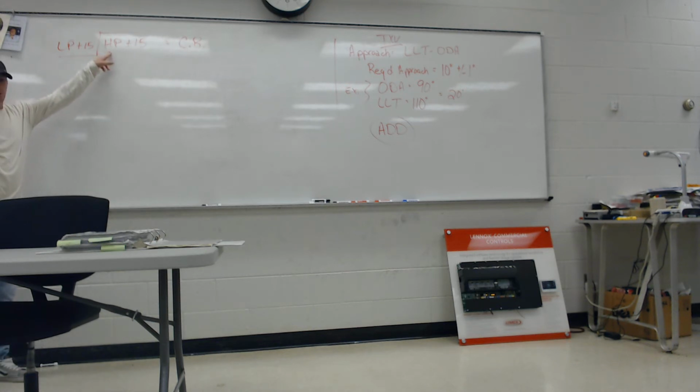What dictates head pressure? Outdoor ambient. Outdoor ambient on air-cooled stuff, right? Whatever the load is on that condenser. We're talking air-to-air stuff right now, so it's going to be outside air temperature. What dictates suction pressure? Load on the evaporator. Since we're talking air-to-air stuff, it's going to be the return conditions, temperature and humidity.